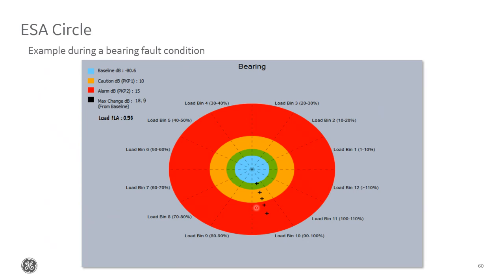For most of the installations that we have installed at the moment, generally you'd put it in service and then just leave it run and make sure there's no alarm that shows up on the front display saying an ESA operation occurred. Some people actually pull the Modbus registers for those alarms and just look to see if an alarm comes up that way. You don't actually need to go in and look at any of these screens unless you specifically want to see what's going on in more detail. Otherwise, the relay will give you an alarm when something happens. It'll be pretty obvious.